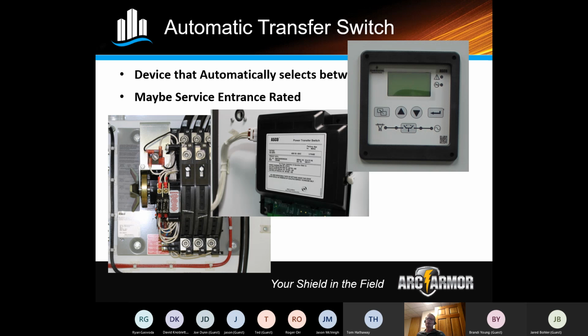Most of the transfer switches that we are using are what they call the delayed transition. A delayed transition transfer switch just means that there will be a drop in power switching between utility power and generator power, and generator power back to utility power. They do make closed transition transfer switches. They're extremely expensive, and those have a zero delay, so they're basically a bumpless transfer going back and forth. So typically in our industry, we're going with what they call an open transition. So there will be a dip in power. So when you're designing panels and going through control circuits, you need to make sure that you take that into account so that you don't automatically have a whole bunch of equipment starting at once or not starting at all.